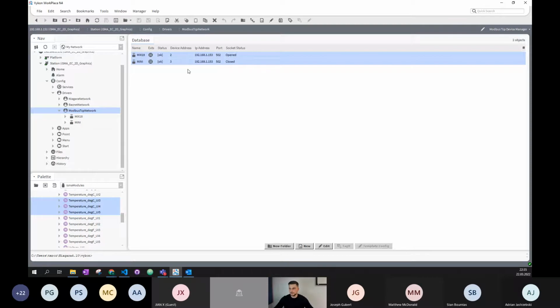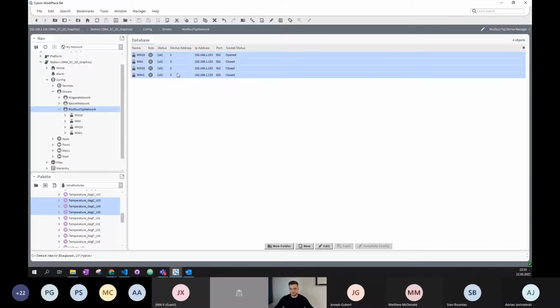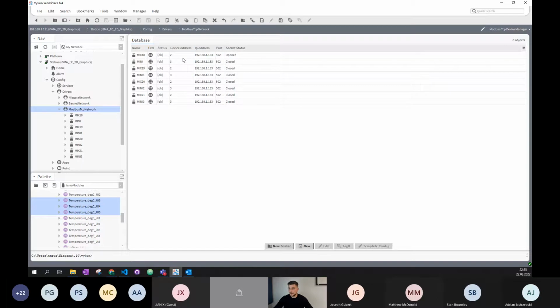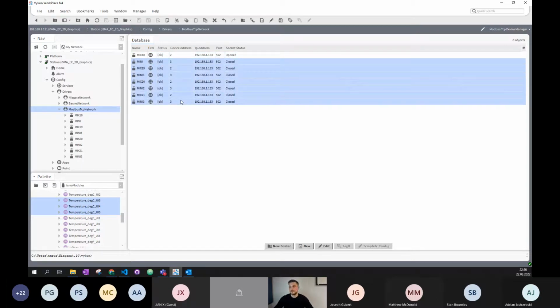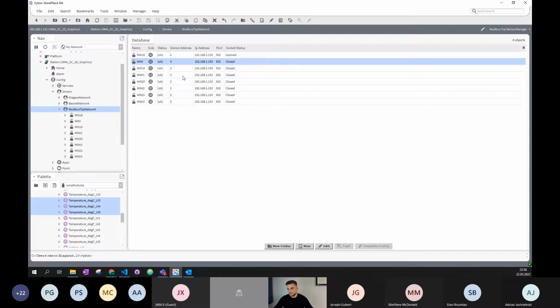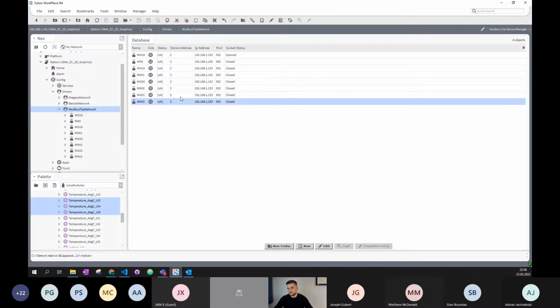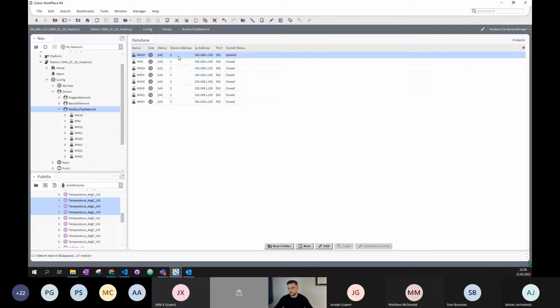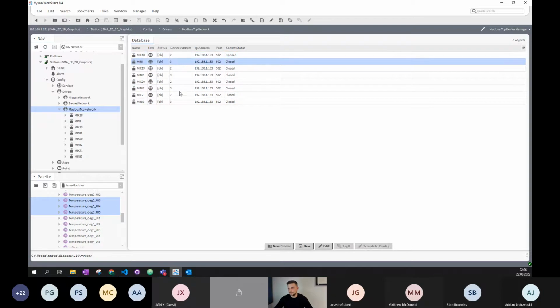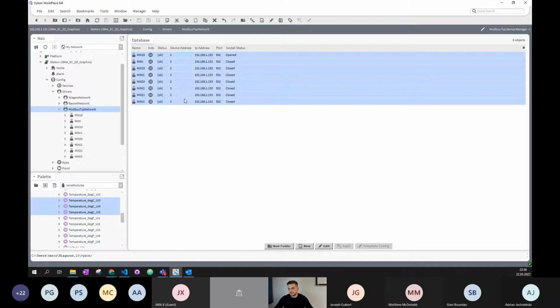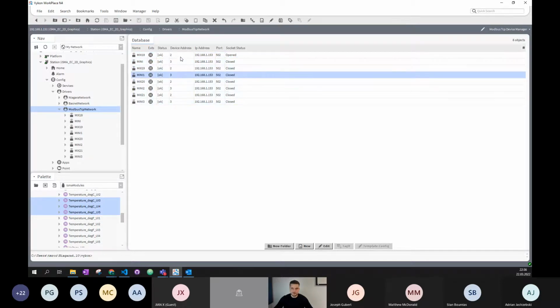Imagine a situation where we have one device, and then 7 devices connected over RS485. This can happen without any problem in a real building. So right now we have 8 sockets opened where the limitation is 4. This will cause communication problems, major ones.